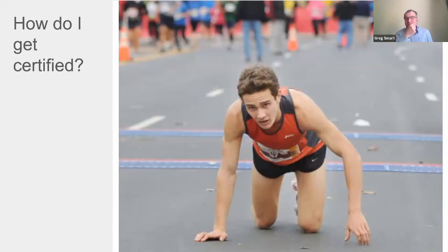So the short answer to the question, how do I get certified, is you create a technical file. And the technical file is really the summary of the body of evidence that you've followed the regulations, complied with the regulations. And so for the remainder of this presentation, what we're going to do is drill into what you need to do and what you need to include in your technical file to demonstrate that.